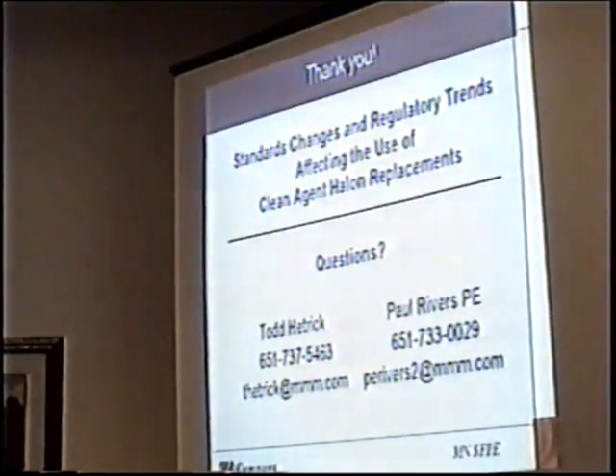So to remind us again, we looked at this Novec a couple of years ago when we put on a demonstration. But if I remember correctly from that presentation, that particular liquid is environmentally safe, correct? That actually was one that was a comparison. But that's one alternative to Halon, one alternative to HFCs. Like I said, there are a number of alternatives. You have water mist, there are a number of manufacturers, all using water mist, inert gases, and a number of different technologies. As an in-kind replacement, yes, that's a sustainable alternative to HFCs and Halon.